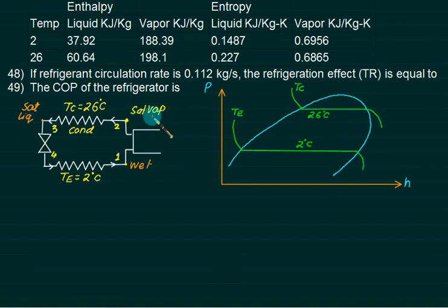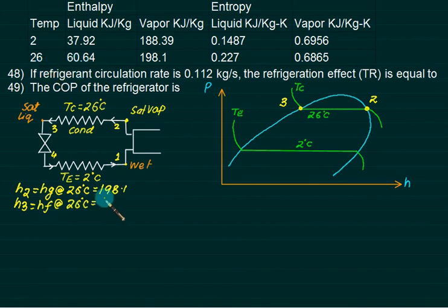The condition is known as saturated vapor. We can locate saturated vapor or saturated liquid on these lines. Point 2 is saturated vapor at temperature 26, so this point is fixed. The enthalpy value equals Hg at 26, which is 198. For saturated liquid, this is point 3 at 26. Value of H3 equals Hf at 26 degrees Celsius, which is 60.64.